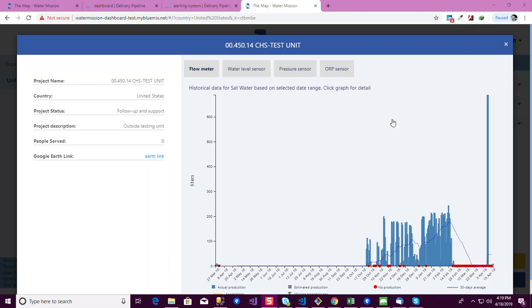First of all, I will start with the ORP. We use the ORP formula and the ORP sensor installed against some assessment, with the low calibration and high calibration values of that sensor. For the pressure sensor, we use the low calibration and high calibration values of the pressure sensor for that project. For a generic sensor on port 2, if we have any other 4-20 milliamp sensor on port 2, then we use the low calibration and high calibration values of that sensor in the ORP formula.